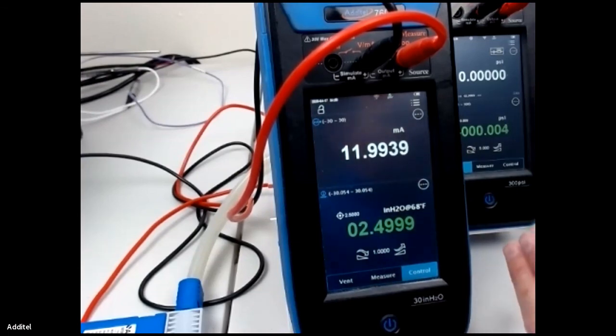We have a middle unit, which I didn't have here, which was the unit I showed you how the batteries change in and out of. That one has a range of basically minus 12.5 PSI to 35 PSI, so you can put modules in all the way across the range, down to as low as 10 inches of water up to the CP35. And then we have the one here in the back that will go from minus 12.5 up to 300 PSI, so we can cover a really wide range.